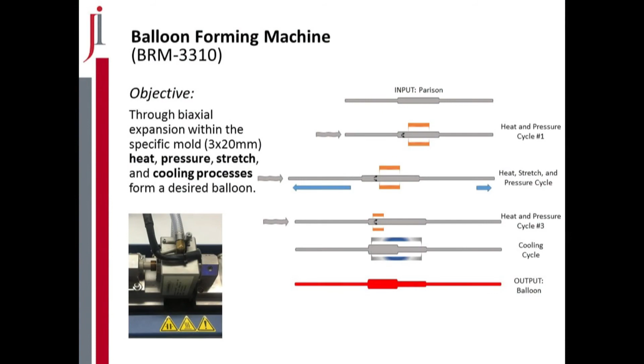So then we look into how we can test this balloon. How do we ensure it's a good functional balloon? How is it going to be a quality product? That's when our hydraulic pressure tester comes in. In its name, we use pressure and water. You attach it to the machine with a two-way burst fitting. You purge out the air bubbles, so you push the air bubbles out to get the best and most accurate reading of pressure, as this machine tests for burst pressure, compliance, and leaks. And then there are failures, so there are alarms that will sound if there's a leak or a burst that the machine will indicate to the user.